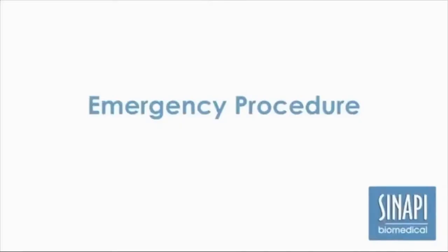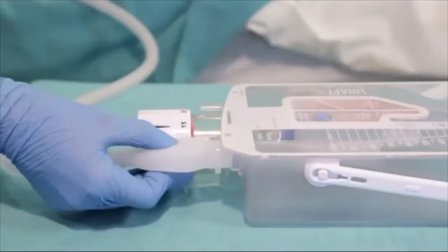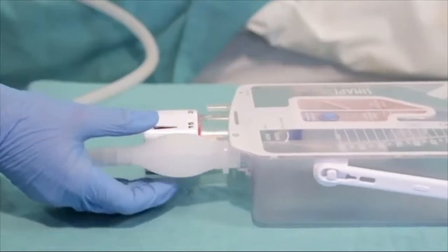When the chest catheter is inserted out of theatre, confirm its position as follows. Once the chest catheter is connected to the Sinapi chest drain, depress the bulb. The bulb must initially re-expand, confirming that air or fluid is draining from the pleural space.